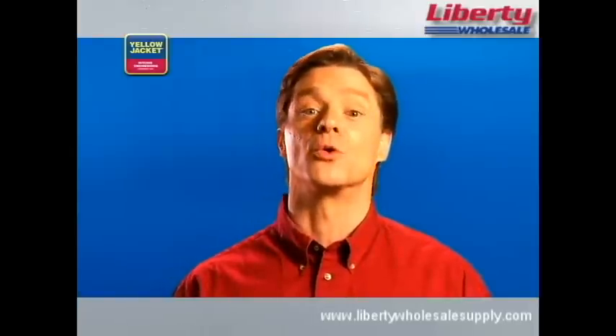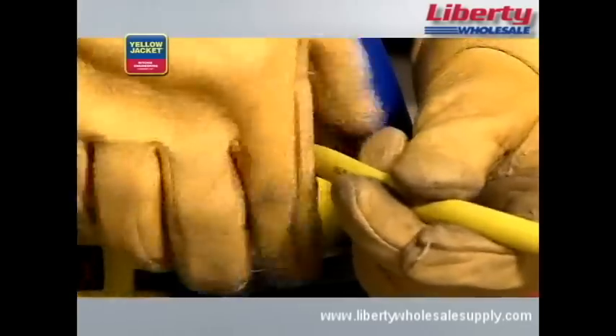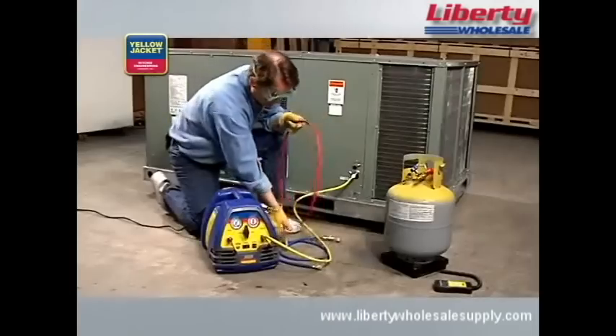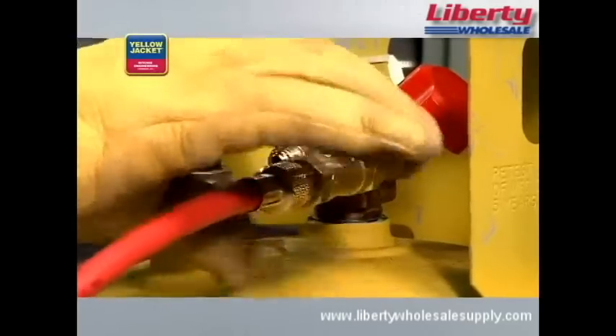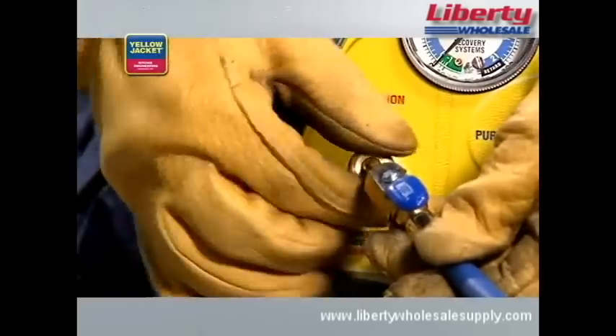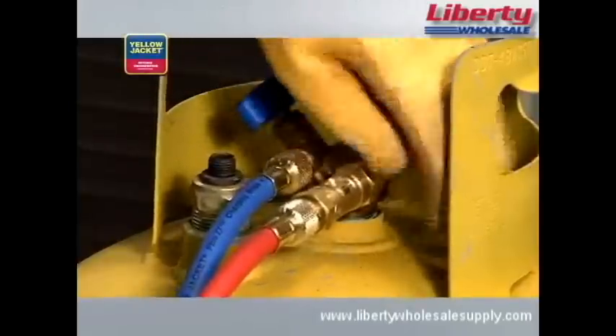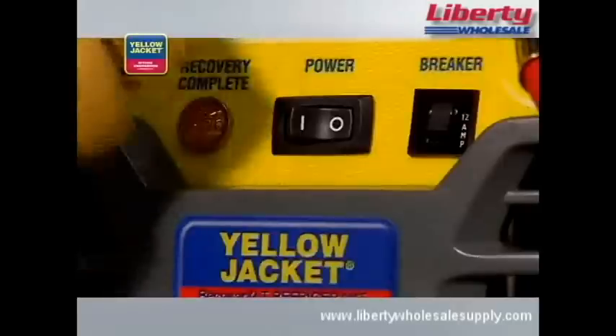Once you have everything you need, you're ready to get started. First, turn off the power to the system you're servicing. Next, connect a hose from the suction port of the recovery unit to the vapor side of the HVAC system. Then, connect another hose from the liquid side of the HVAC system to the sight glass and onto the liquid side of the recovery tank. Finally, connect a hose from the vapor side of the recovery tank to the discharge port of the recovery unit. Here's what the final connection should look like. Once all connections are hooked up, purge the hoses of non-condensibles before starting recovery. Now, open the valves on the recovery tank, then turn the selector valve on your recovery unit to vapor and turn the recovery unit on.